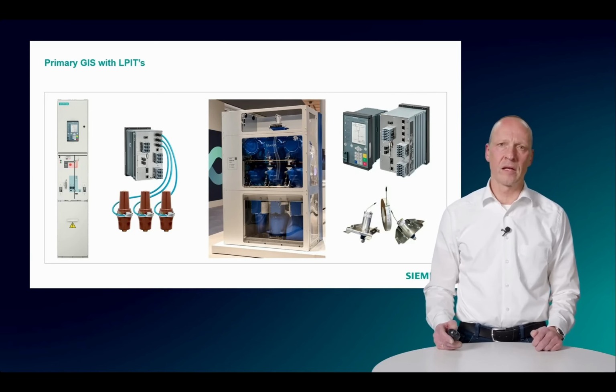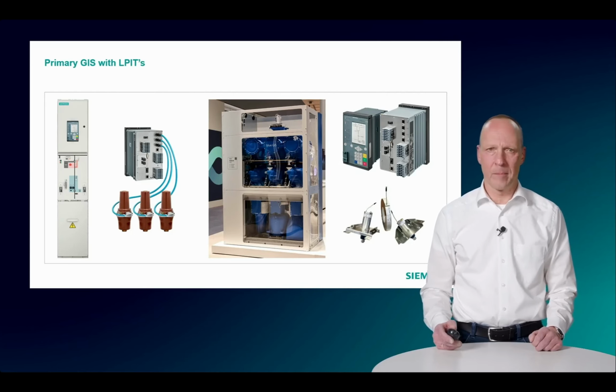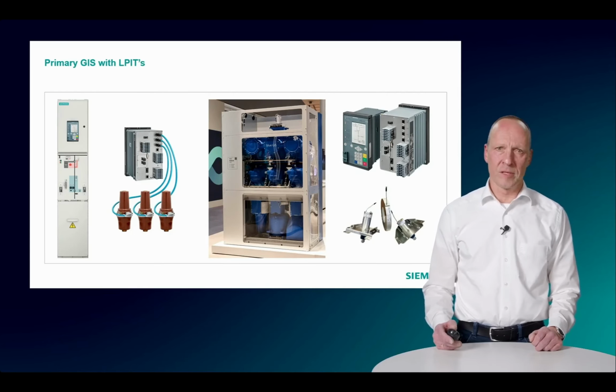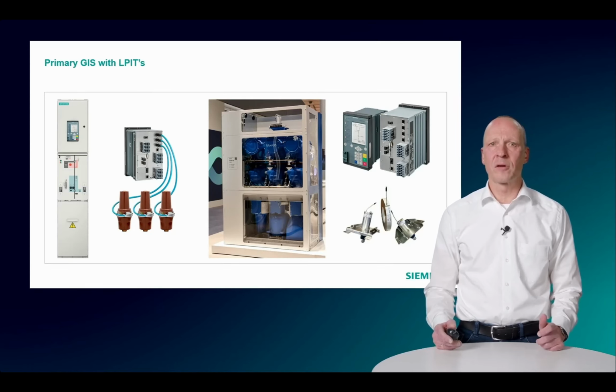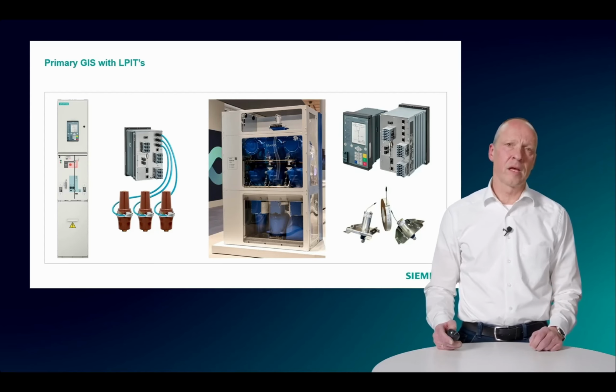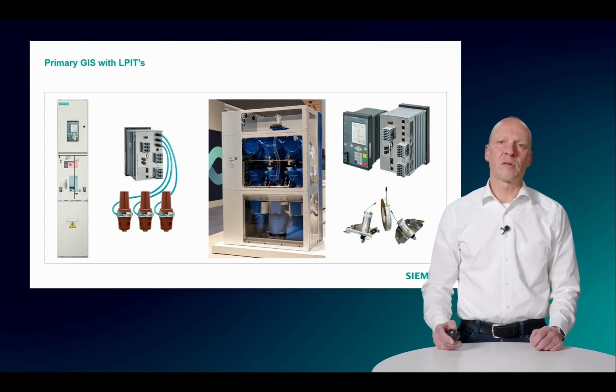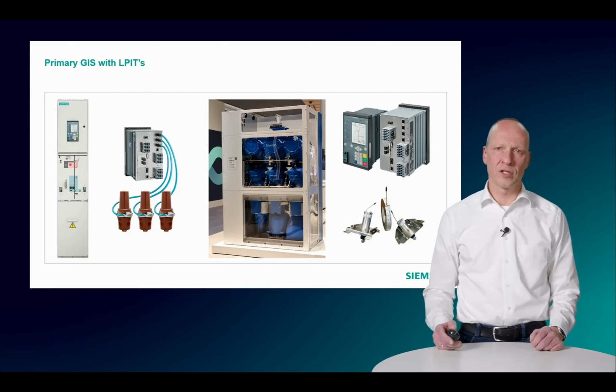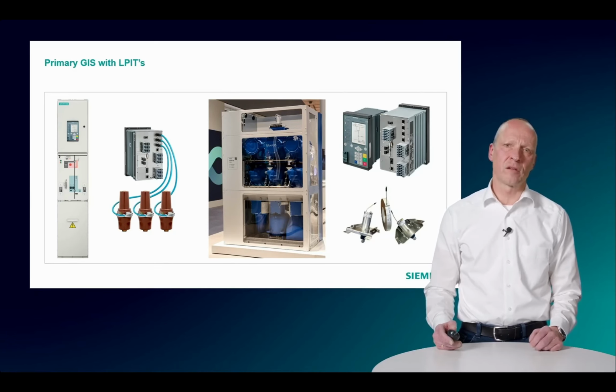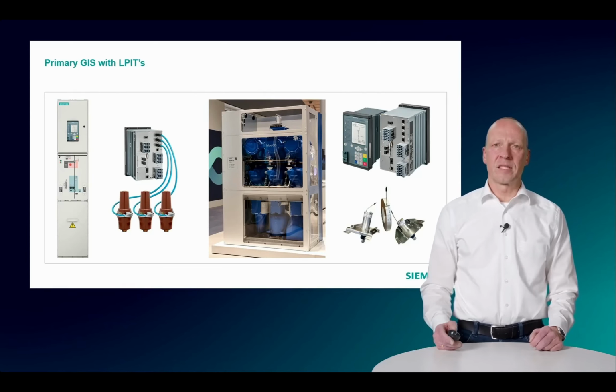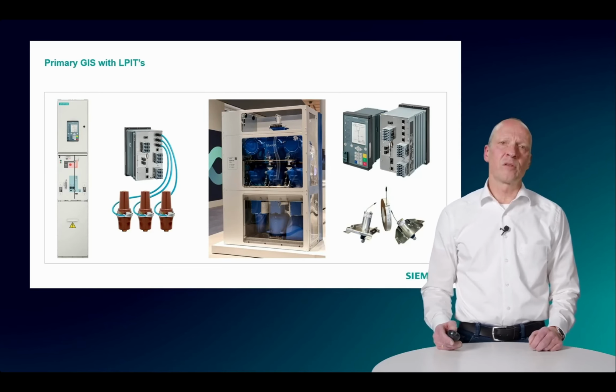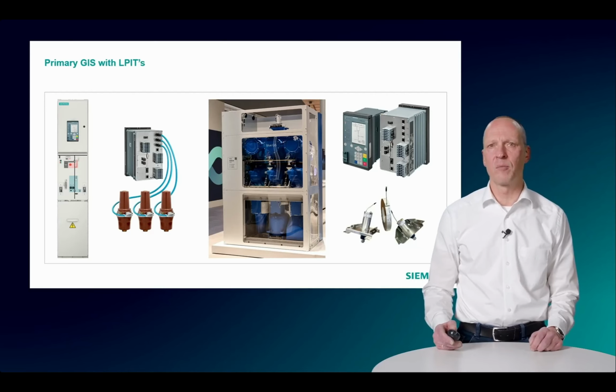savings, and technical innovations, as explained already earlier. Low power voltage transformers are immune to grid disturbances, such as ferroresonance phenomena, and therefore do not require the use of damping resistors. Low power current transformers in Rogowski technology demonstrate linearity throughout the whole measuring range, even up to the full rated short circuit fault current without any saturation effects. For our NX Plus C 24 Blue GIS, we are able to provide also the C-bushing solution, as already shown in the 8DJH24 Blue GIS.